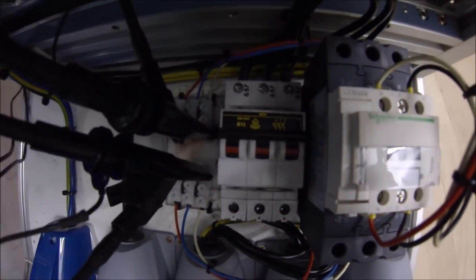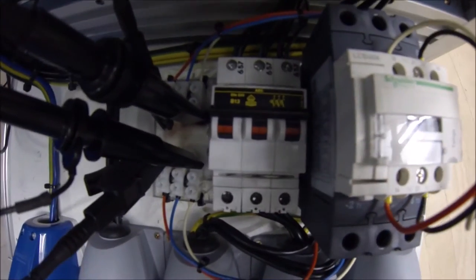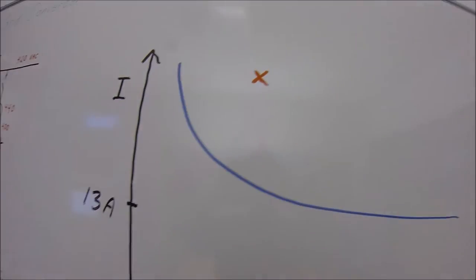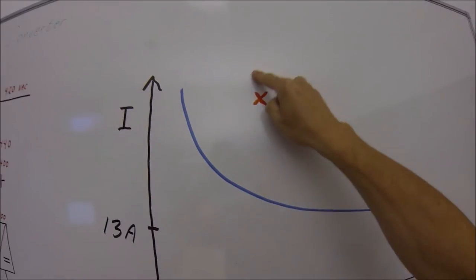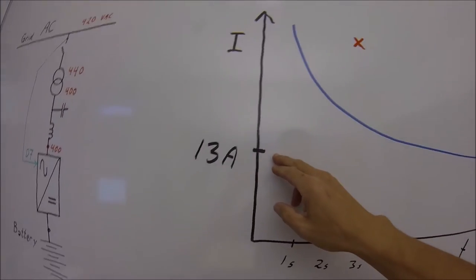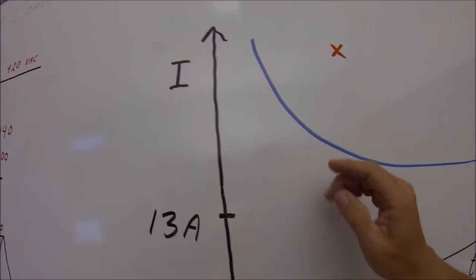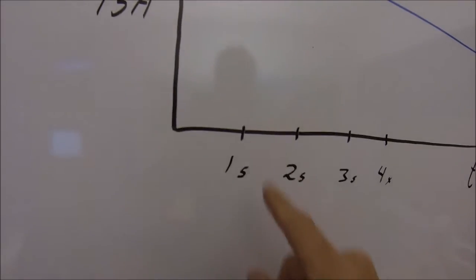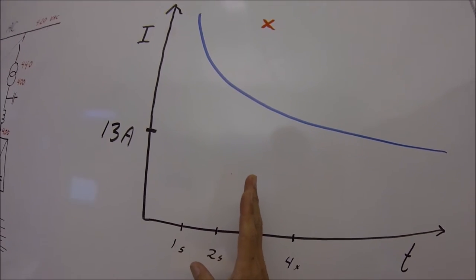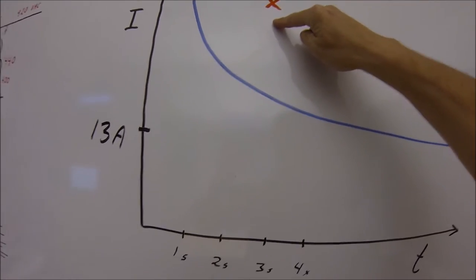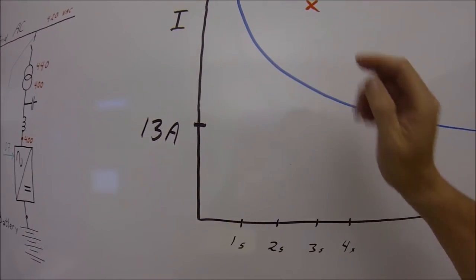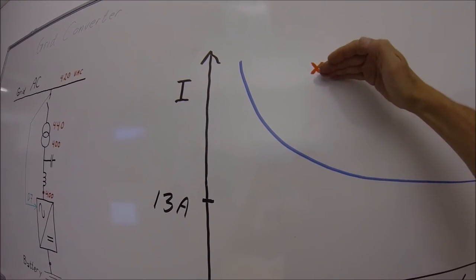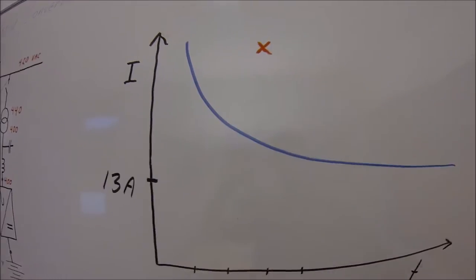The fuse that we just tripped is this one. It's a 13 ampere B characteristics and what happened was that with our drive we created a current, a controlled current that was above this curve. It can sit continuously with 13 amperes and it can sustain some high current for a very short time but we kept the current going for enough time and high enough current for it to trip. So this is how to calculate the selectivity. You need to sustain the current high enough, long enough to stay above this curve and it will trip.